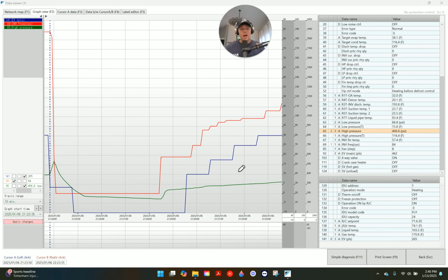Well, what happens when hot gas is going to a valve and it goes to close 2/3 of what it was already open, right? You get restriction, you get backup, right? So the head pressure goes where? It goes up, right? And now, as I move forward with this data on this next point, I've got 472, right? And then by the time I get right past that point, the compressor goes to slow down. It goes, whoa, wait, a problem. We have a problem here. And the trips kick.